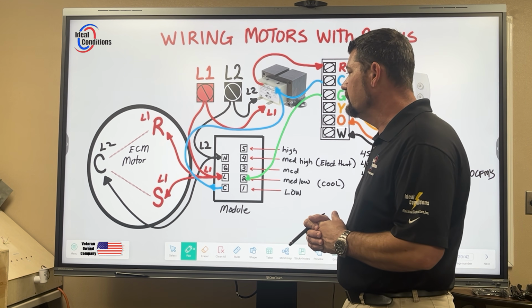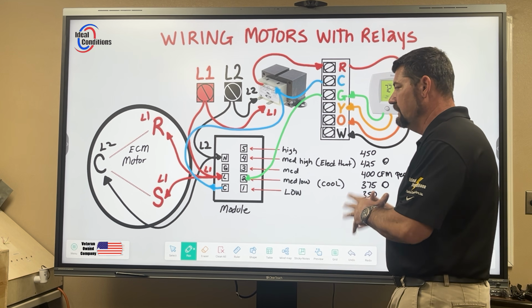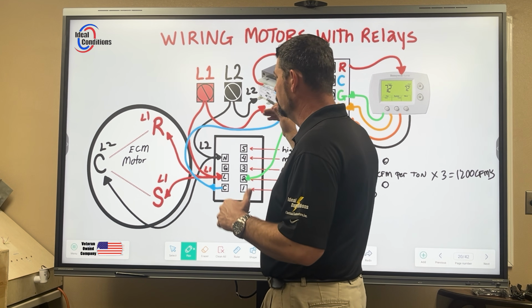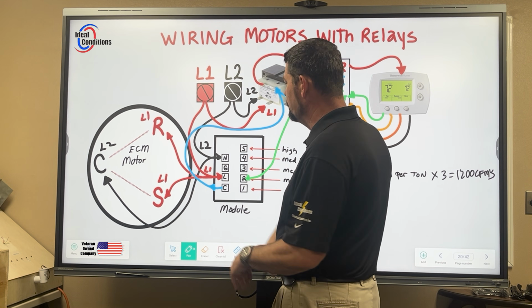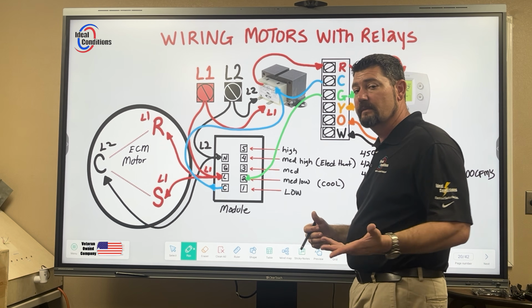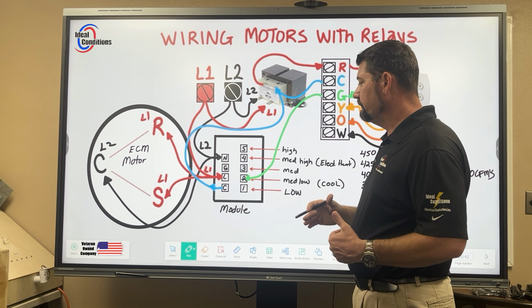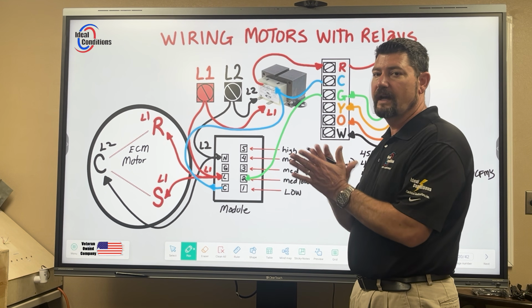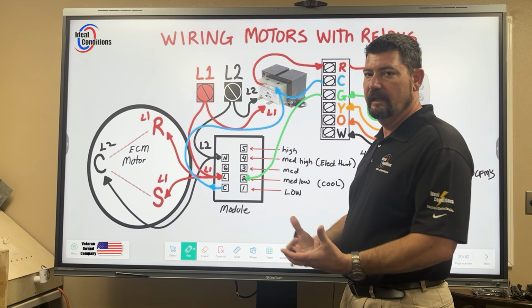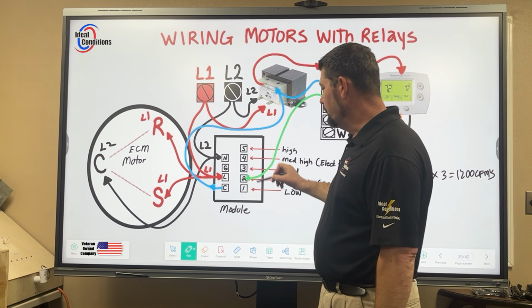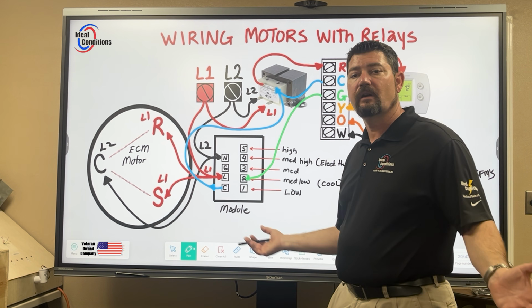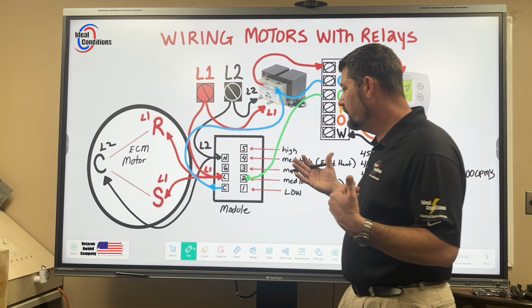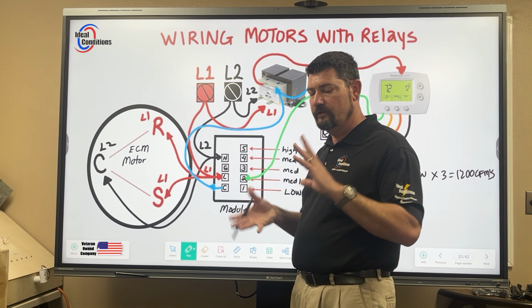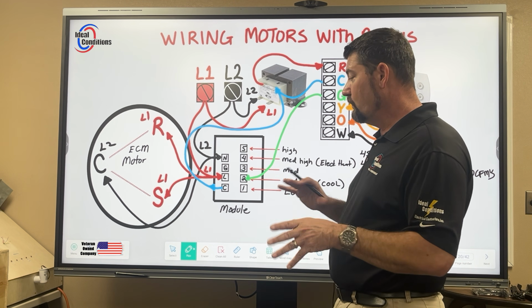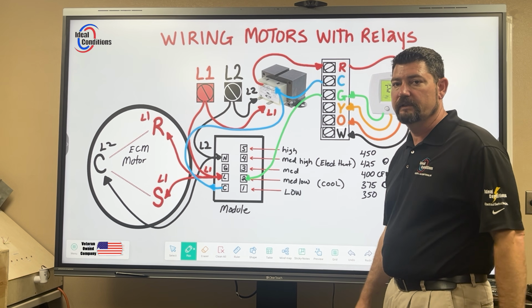A lot of times you can just de-energize the air handler breaker. L1, L2 will lose power. It pretty much resets it. You can turn it back on. And a lot of times what you'll see is it'll come back on and that module will not be engaged and allow that motor to run. And the moment you apply power, sometimes the problem goes away. Well, if you have already got to that point and you temporarily have got it working right, you still need to order the component that you need.